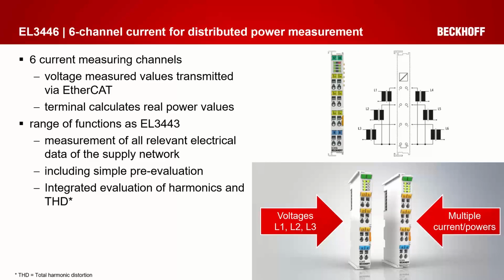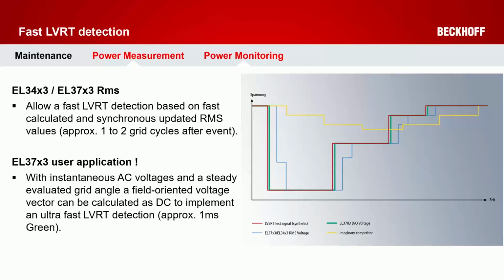This also reduces the cost. Another application, which might be more interesting, and which I found out in my career is one of the most difficult points in a wind application, is to allow the wind turbine to ride through a low voltage dip. We call it LVRT capability. And this voltage dip is mainly triggered by a near grid fault. Modern grid codes require the LVRT ability in a defined voltage over time envelope. Especially the earliest possible detection is essential to prevent a drivetrain overspeed, especially in high load wind operations. So even a 10 millisecond delay in detection could already give you an overspeed. So essential is a very fast detection.